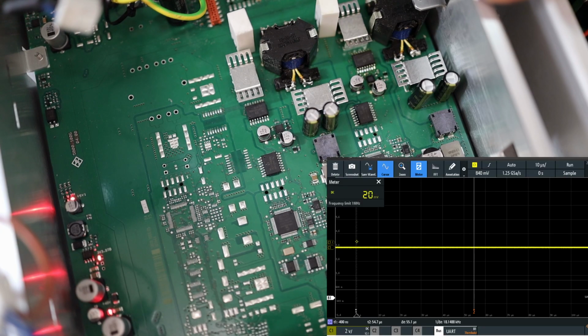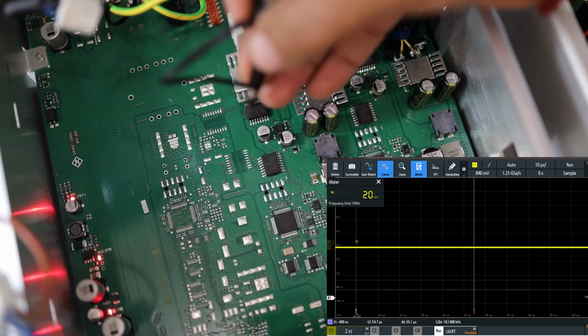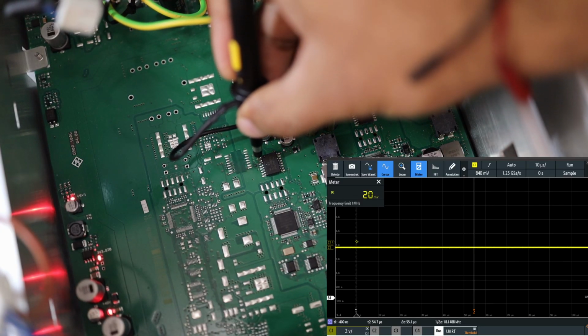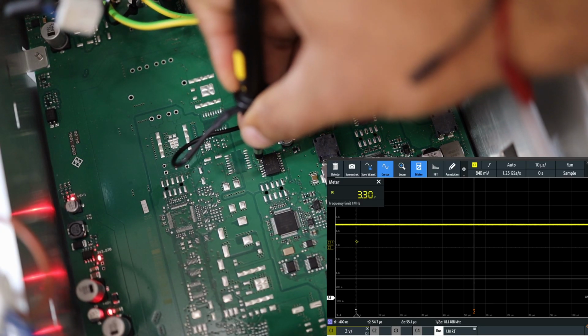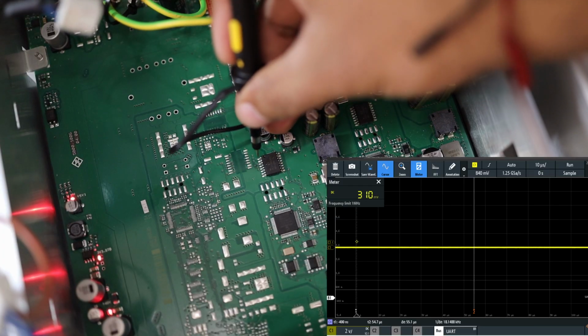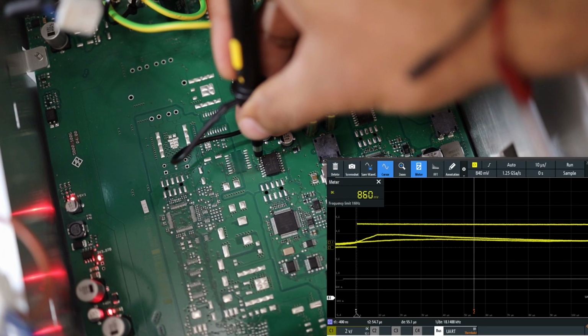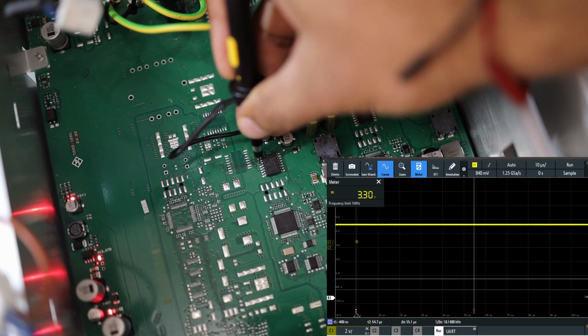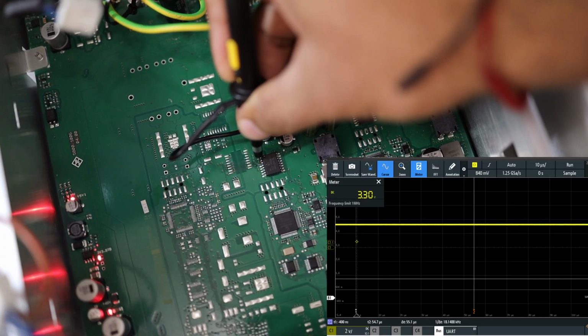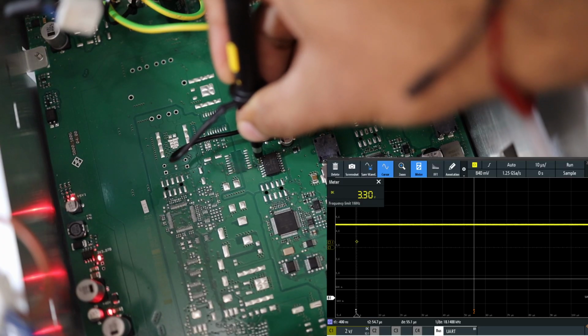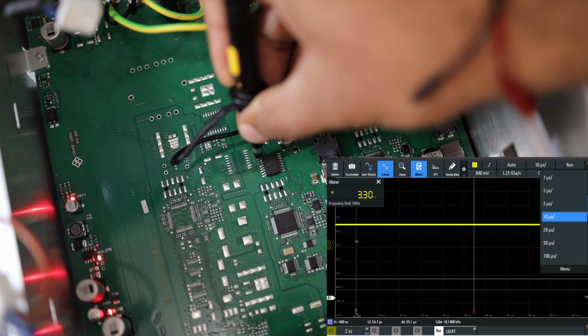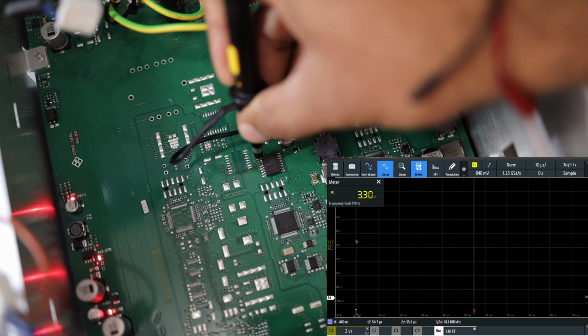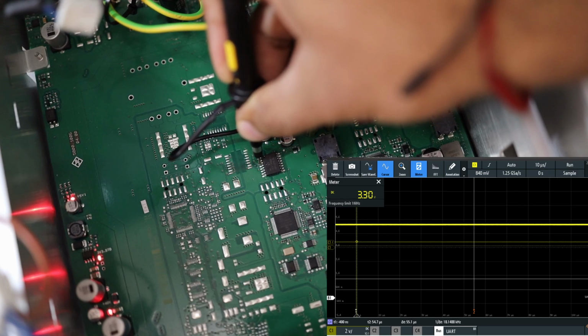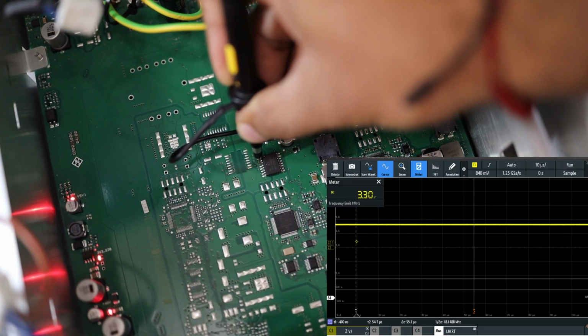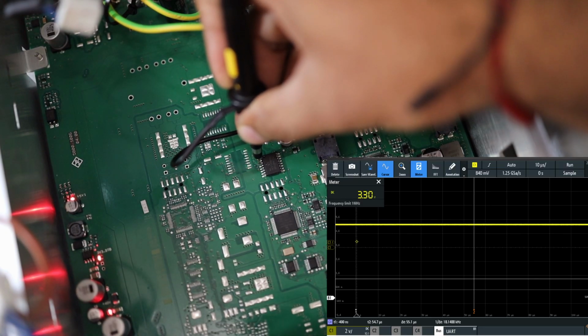So the first thing we will check is whether these control signals are coming. And check on number 3, and you can see on the scope that pin number 3 is constant high, and there is no activity happening on this. I'll set it to normal mode so that we can see if the trigger is there. No activity whatsoever, the trigger is not there. Okay, so there is a possibility that the microcontroller is faulty, or the connector is faulty. It's not sending anything at all.